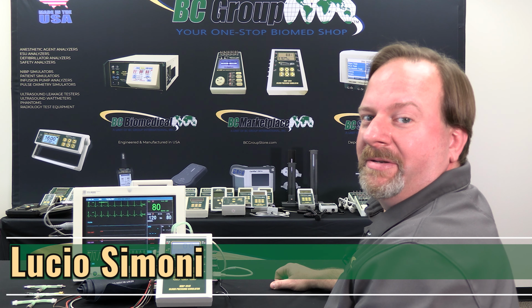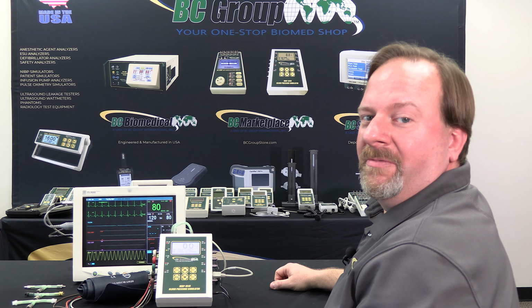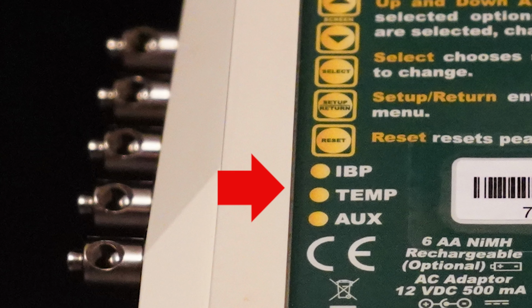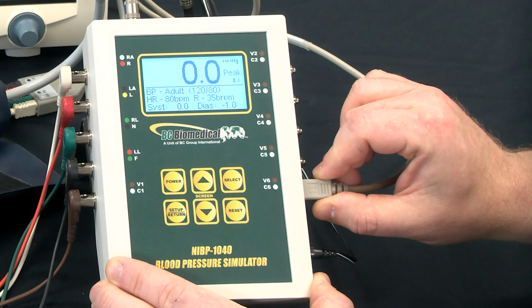I am the engineering manager for BC Group, and in this video we'll be demonstrating temperature simulation using the NIBP-1040 series simulator. In this case, we have our temperature cable plugged into the middle connector on the side. And if you look at the back of the unit, the label will actually identify the three connectors on the side and what they're used for. In this case, the middle one is for temperature, so we have our cable plugged in.